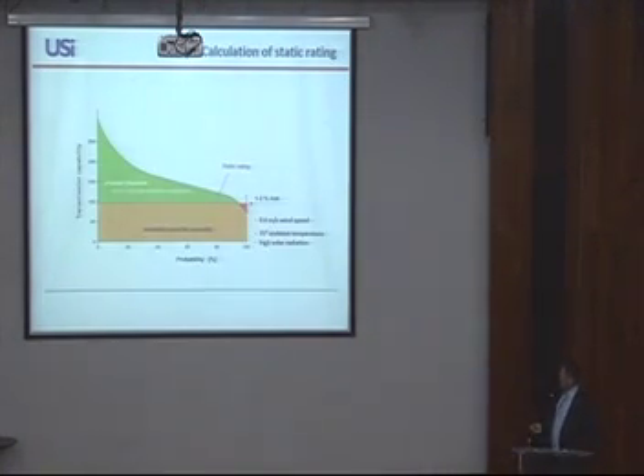But you still have this big amount of green area which you cannot use. And with DLR, what you want to do is measure the real capacity of a line at each time, so I can use this for operational purposes. The point is, I mentioned the 75 degrees. If you follow this probability curve, this is exactly 75 degrees in that case. So you can use all that without exceeding the maximum temperature due to the additional cooling here.